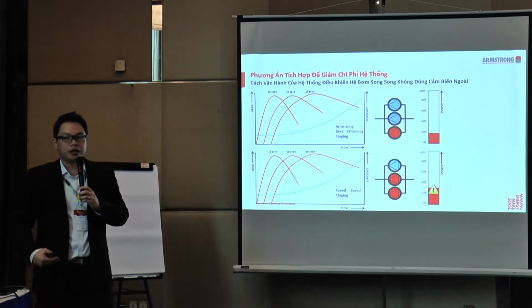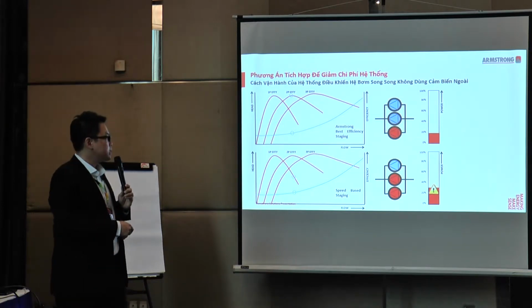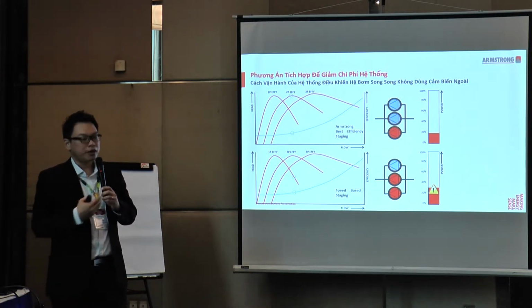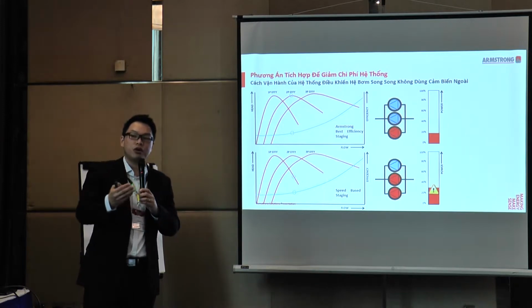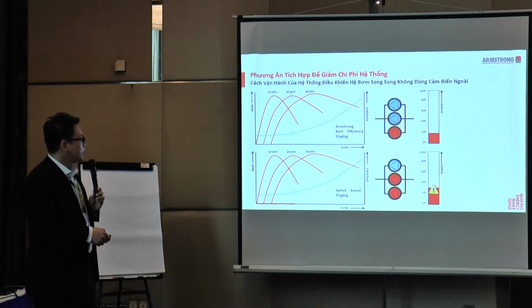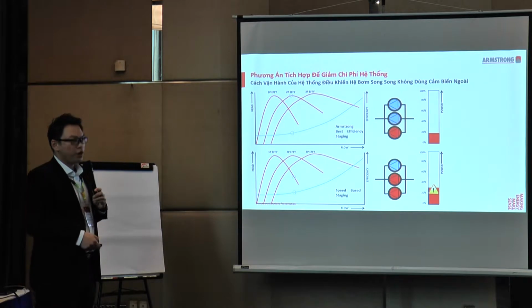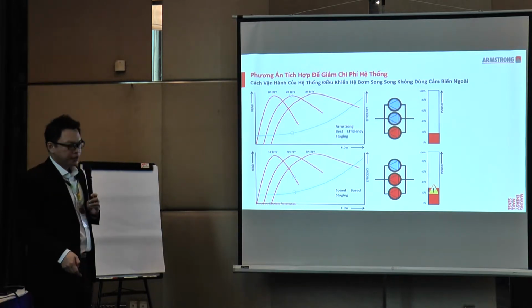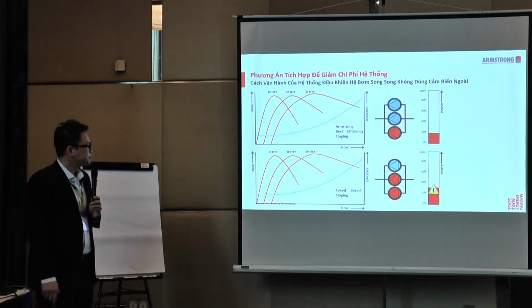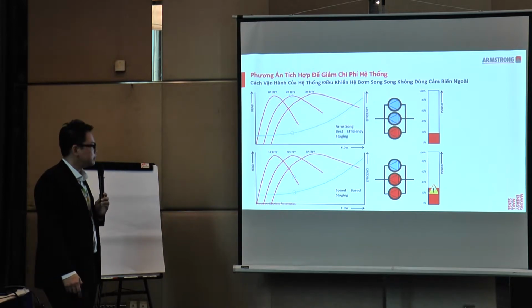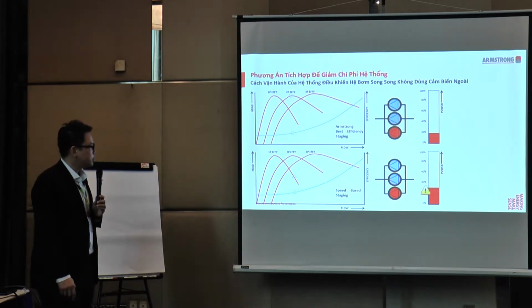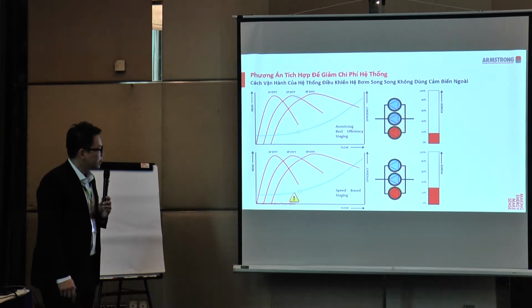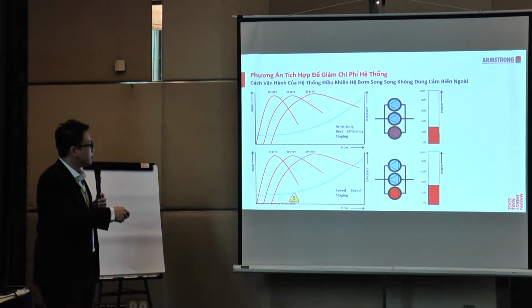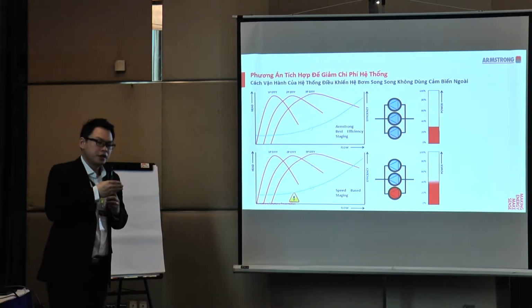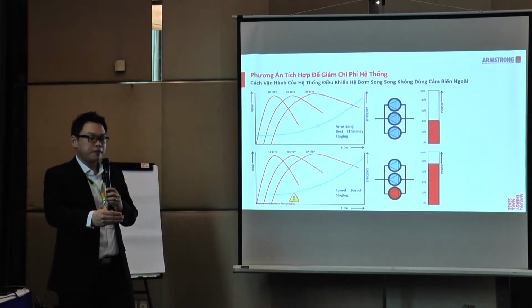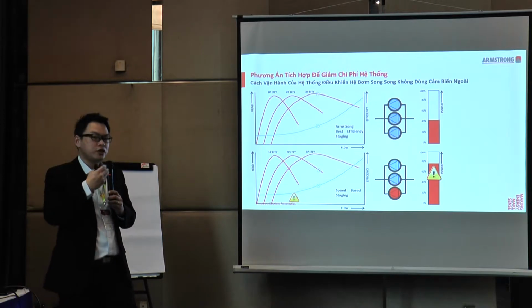Again, this means that in terms of operating cost, our best efficiency staging pumps methodology helps your owners or your clients save money. Here you will notice there is this warning sign. I'm going to put this warning sign at this point on the graph. These are the points at the intersection of the first and second pumps' efficiency graphs. This is where the next pump is going to turn on.